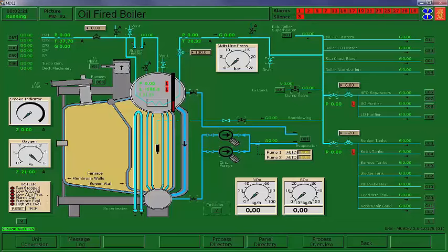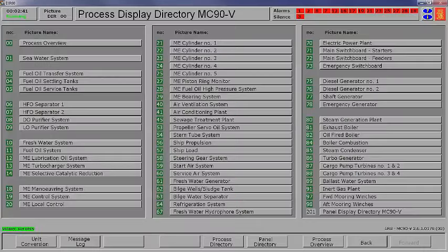So we want our de-superheated steam stop wide open. We need to open for the circ pumps. Their suction is from the mud drum, returning back to the steam drum. All right, we've got that. Now we've got to put some boiler water in there.